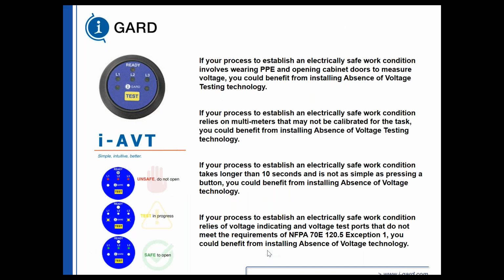So your process to establish electrical safe work condition involves wearing PPE and opening cabinet doors to measure voltages. And again, we've seen that this is when people get hurt, because this is when they're exposed to the hazard. They have a restricted approach boundary, but they're still getting hurt, still dying from testing the safe condition that they should have. If your process is to establish an electrical safe work condition, you have to use multimeters and calibrate for the task. We're not going to use a 600 volt test instrument to test 5 kV. So you have to select the appropriate test equipment to perform the test.